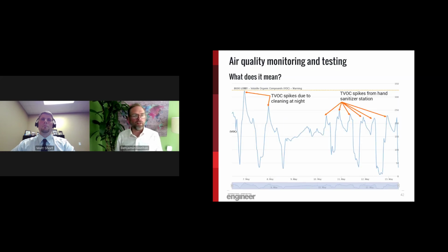And air quality monitoring and testing is something that has really come into play. A lot of buildings would do a test per year and not really know what the data means. Have an industrial hygienist come in and take some samples and see what's floating around on that one day. But now the cost of sensors and the availability of decent sensors that can constantly monitor and trend, and be readily available on a portable device, are accessible and affordable. And so we're seeing people starting to put these sensors in buildings, but understanding what the information means isn't always the simplest thing.